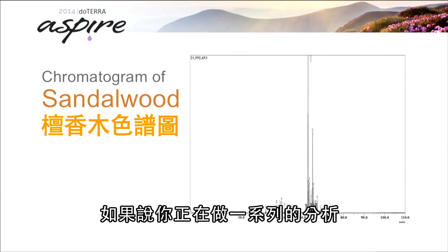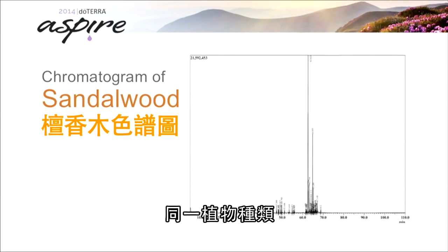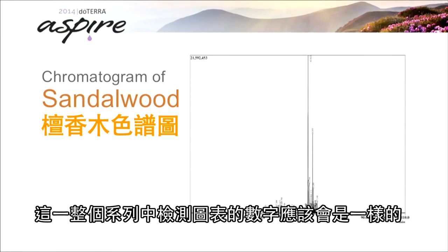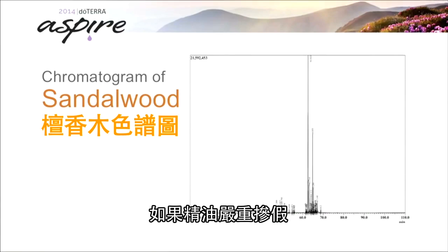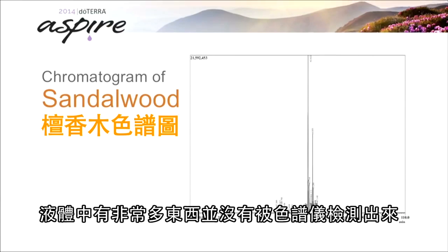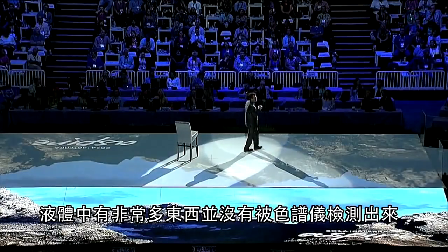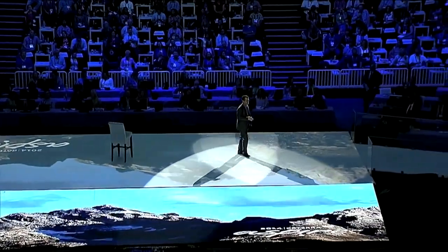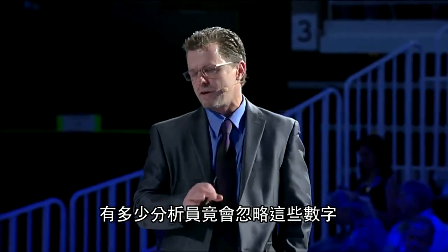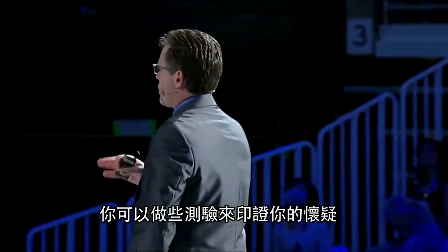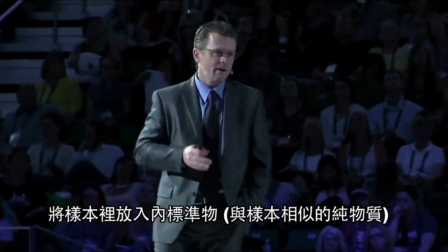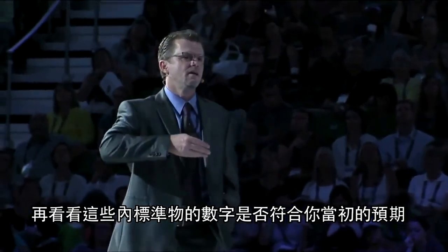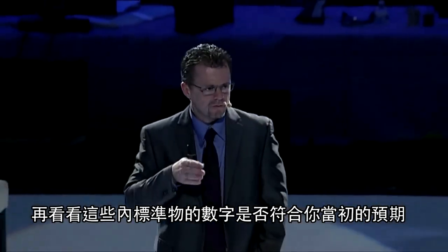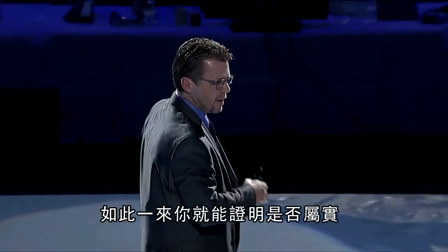If you're doing a series of analyses and it's the same oil, same species, you would expect that number to be the same throughout your series of different samples. When it's drastically cut, that tells you there's a large percentage of that liquid that is not coming off the GC column. And it's amazing how many analysts overlook that number. You can do some further tests to confirm your suspicions by putting an internal standard in the sample and then seeing if that internal standard measures up to what you expected, and that would confirm your suspicion.